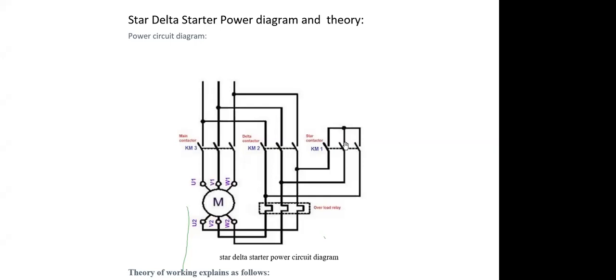So in the initial stage, when I switch it on, the star contactor, I mean KM1 and KM3, gets energized. The motor starts rotating at a reduced speed. Then after a predetermined time delay, star opens, delta closes. The main contactor was earlier switched on, it remains switched on, and the motor runs.